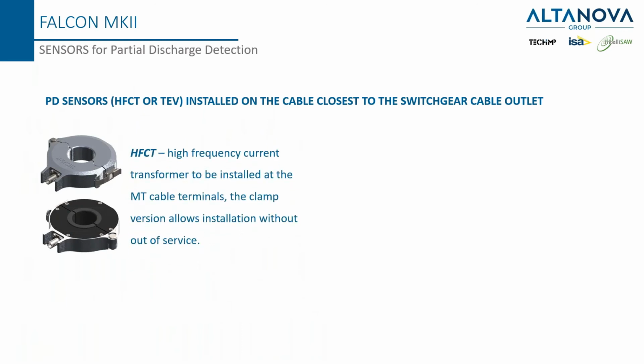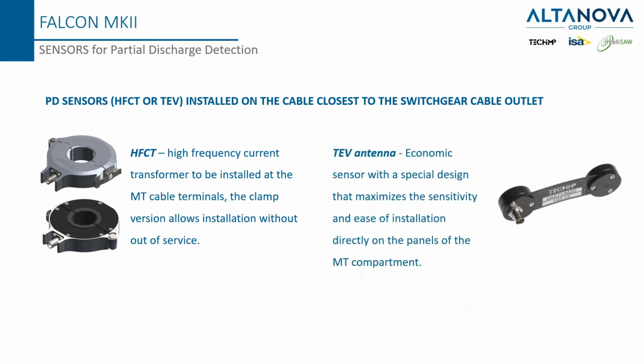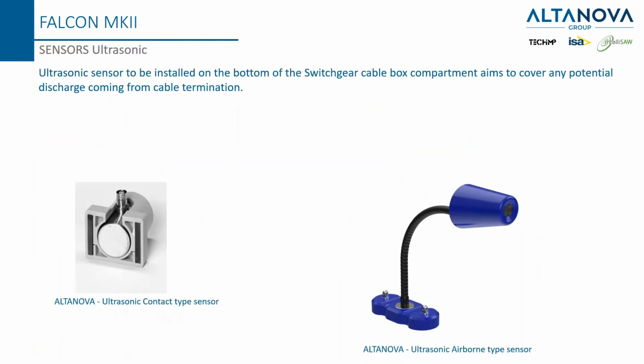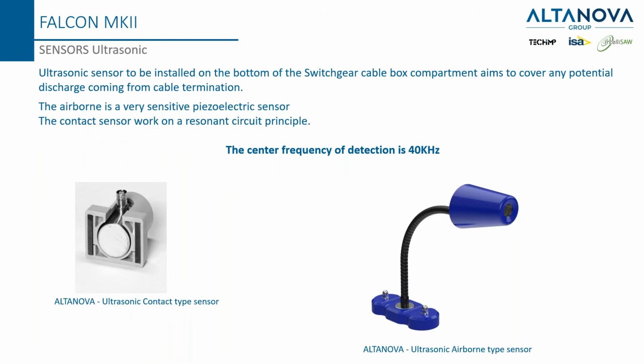Also here, the main sensors used are HFCT, installed on the cable closest to the switchgear cable out, or the TEV, that is the sensor with a special design to maximize the sensitivity and ease of installation directly on the panels of the medium voltage compartment. About the ultrasonic sensor, Altanova can provide 2 different types of ultrasonic, and basically they are installed on the bottom of the switchgear cable box compartment, aiming to cover any potential discharge coming from the cable termination. The airborne is a very sensitive piezoelectric sensor, and the contact sensor works on a resonant circuit principle. Both of these 2 sensors have a center frequency of 40 kHz.